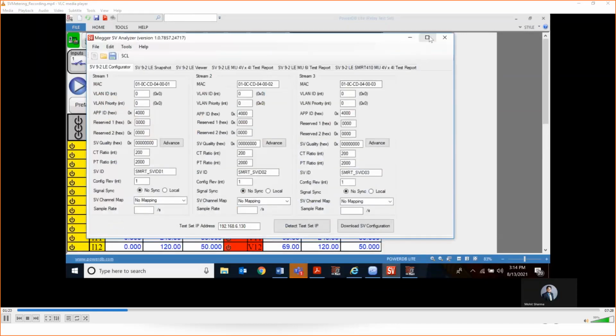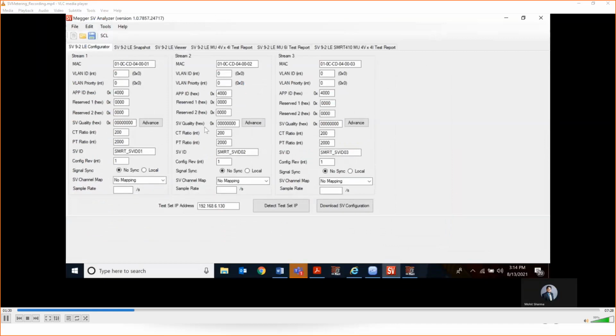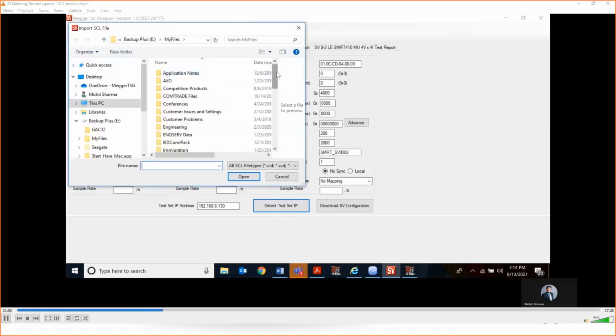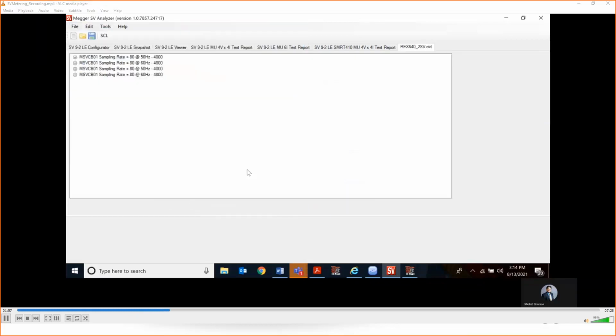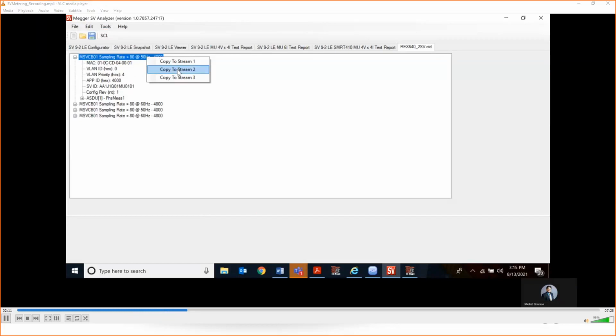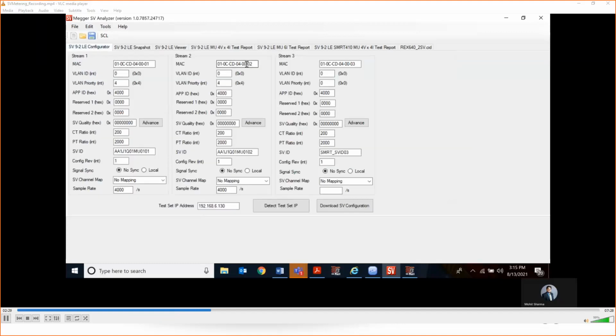Then he will go to the SVA software, sampled value analyzer software. You can see here you have the 3 streams that can be configured manually, or you can just import a substation configuration language file, basically a file to configure these streams. So there are these blocks for the stream that you can just copy to your configurator, and it's as simple as that. This is like the connection of your test plug. Of course, you have to do all the preparation, select the appropriate test mode, and know your whole system. This is just for demonstration purposes.